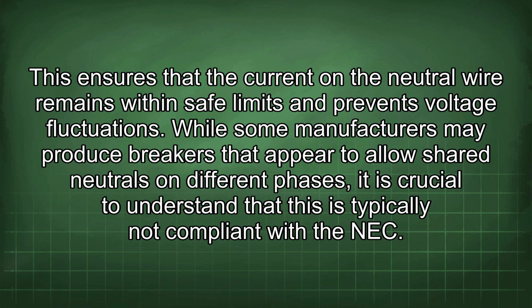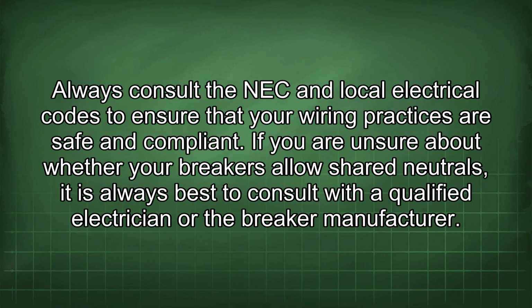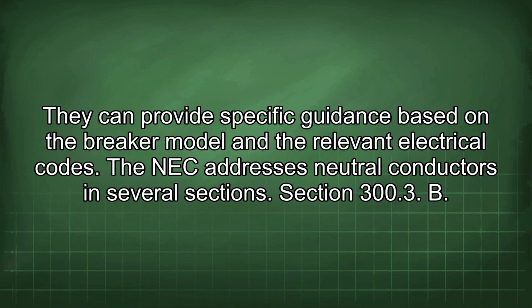While some manufacturers may produce breakers that appear to allow shared neutrals on different phases, it is crucial to understand that this is typically not compliant with the NEC. Always consult the NEC and local electrical codes to ensure that your wiring practices are safe and compliant. If you are unsure about whether your breakers allow shared neutrals, it is always best to consult with a qualified electrician or the breaker manufacturer. They can provide specific guidance based on the breaker model and the relevant electrical codes.